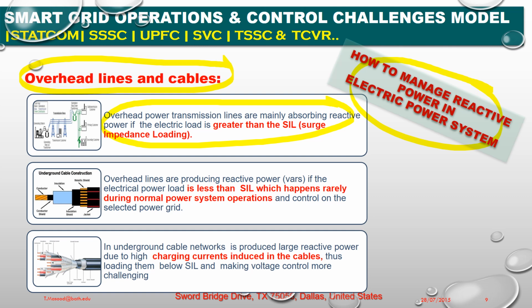Number 2, overhead lines produce reactive power if the electric power load is less than the SIL, which happens rarely during normal power system operation and control of the electric power grid. So it happens very rarely, or you can say it never happens.